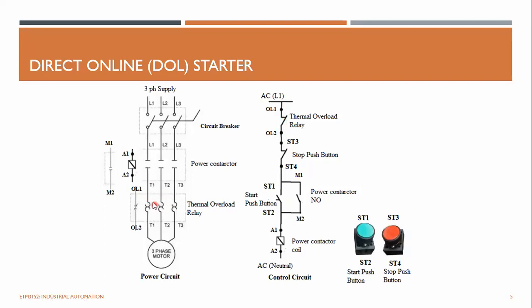So when it is normally running, the thermal overload contact, this one, is a normally closed contact, and no overload happens. If the overload happens, this will open, right? Normally this is closed, so the current is coming from here, and the stop push button is not pressed, which means the current can still come to here. This path is completed. And this is your start button. When you press this one, you close it, and the current is now coming to the A1 and A2 coil, and this is the neutral, right?